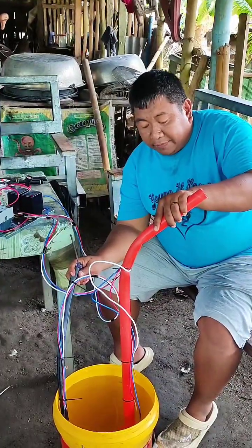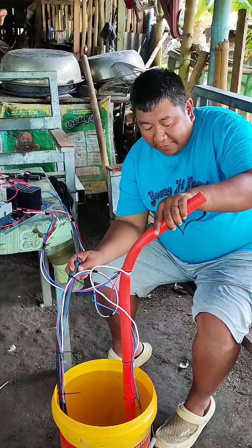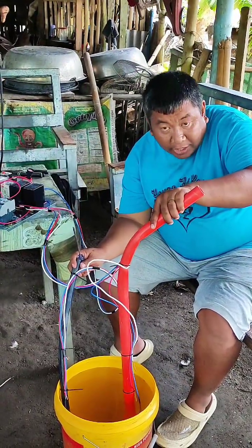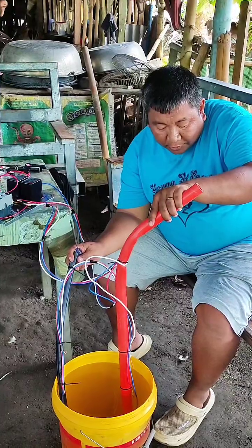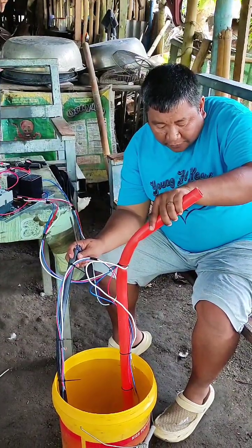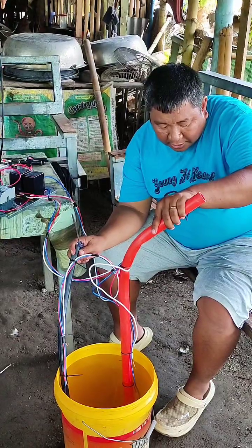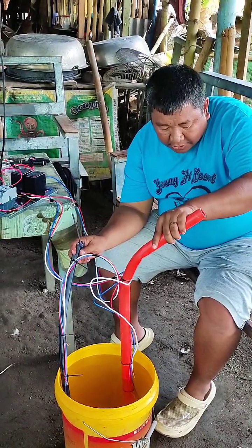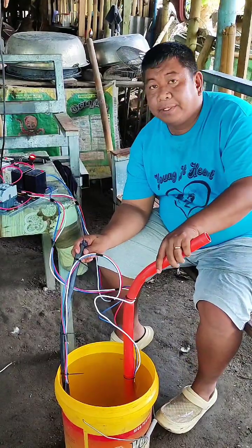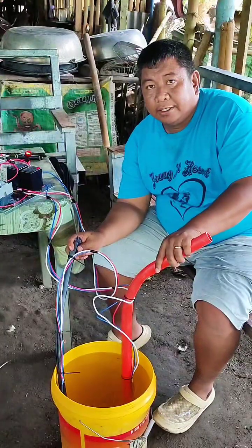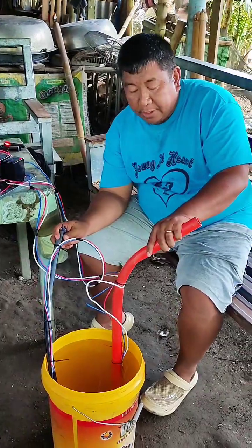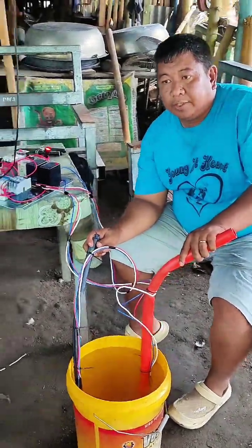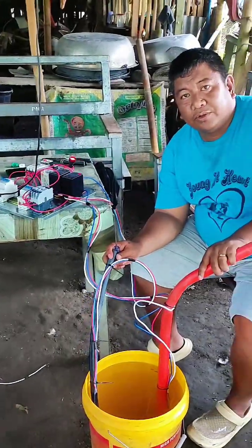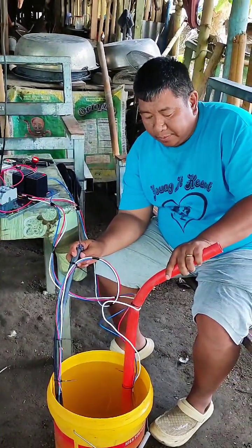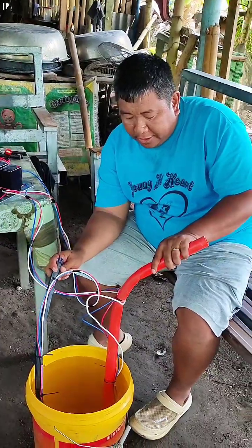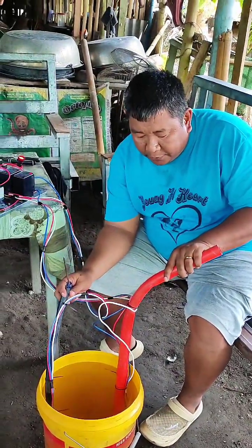What's the remedy for that? If the water comes back to a certain level, let's say that the white probe is the water level, then when it fills up, it will not start up until it reaches that level, and boom, the pump engages again. That is perfect for the well protection for the pump, because the heat will destroy your pump. So then it's a full tank.